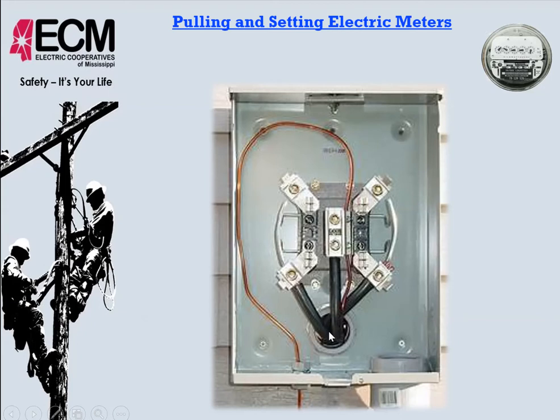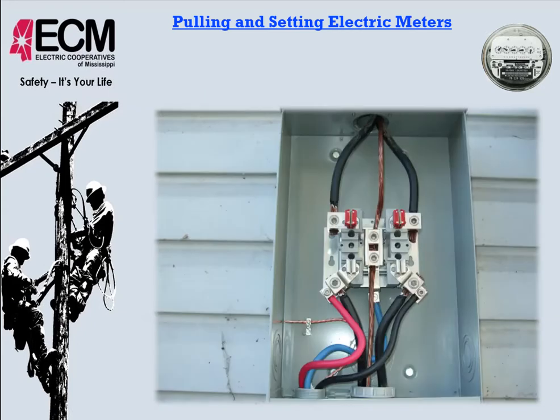Okay, here's another meter base, just showing some of the knots to do. Here again, you have uninsulated wire in with insulated wire. This is going to rub into that. Metal against rubber or plastic, there's a natural vibration there from the wind. Also, the electrons flowing up and down the wire, so that does not need to be bare. Okay, so that's a bare coming from the weatherhead, from up top's an overhead service.